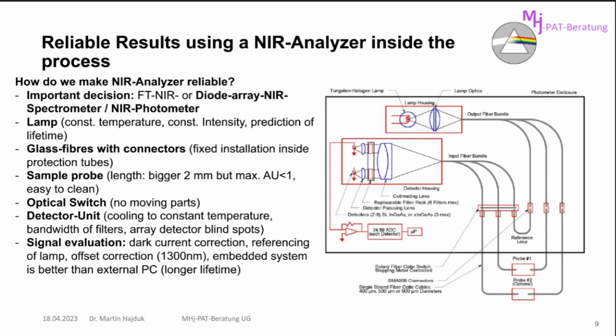So then we have here the signal variation evaluation. Normally, we make the dark current correction. That means there is also a possibility, a fourth point, where no light goes through the switch, and we measure the intensity shown by the detector, and build the difference between the measured intensity and the dark current intensity. And because I'm talking about the problems of the temperature of the filament of the lamp, normally we reference the lamp directly. Then we normally have an offset correction at a point in the NIR spectrum nearby 1300 nanometers, where all organic components have no absorption.